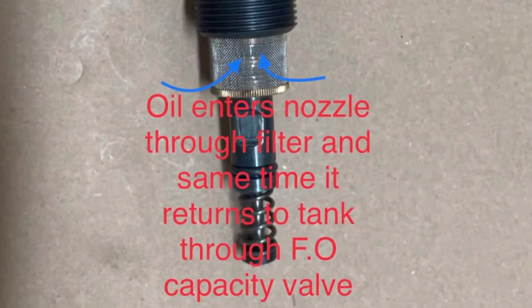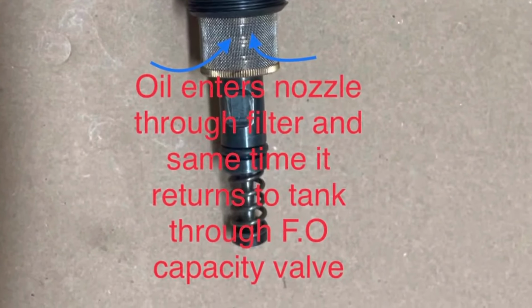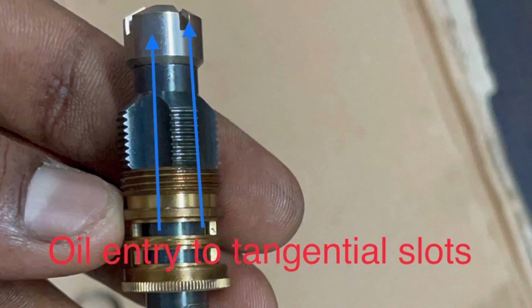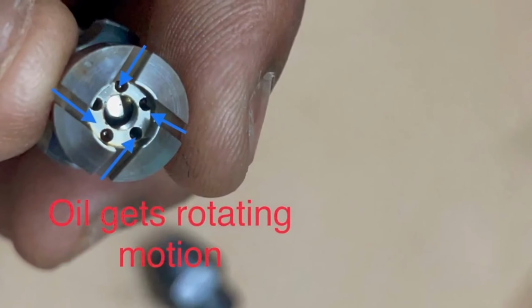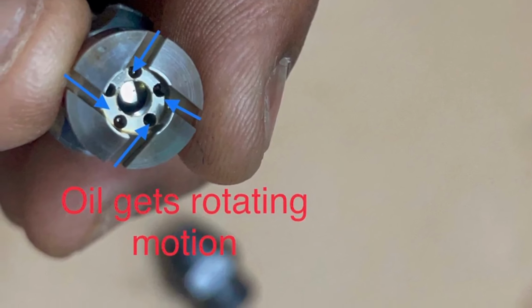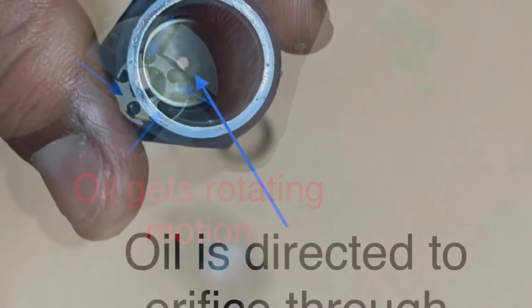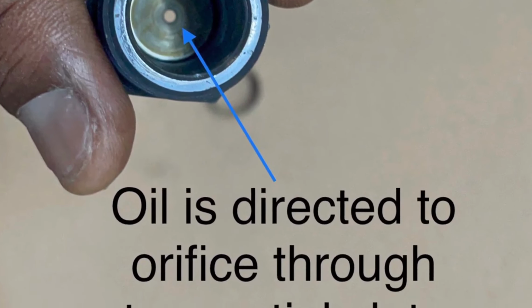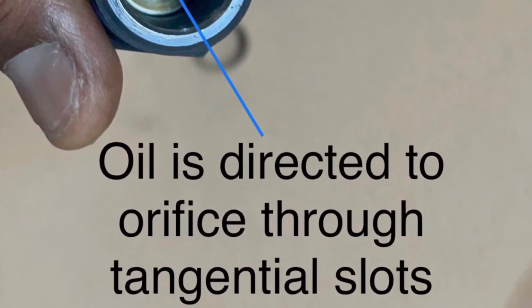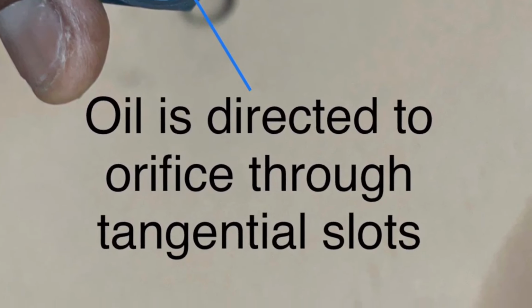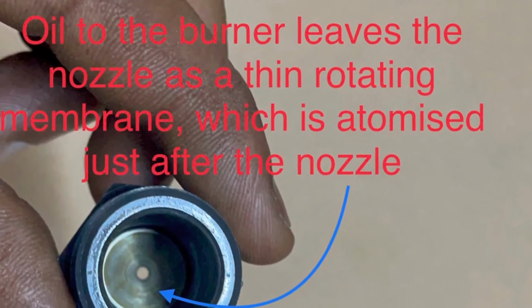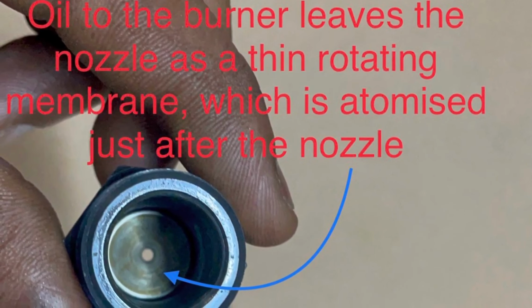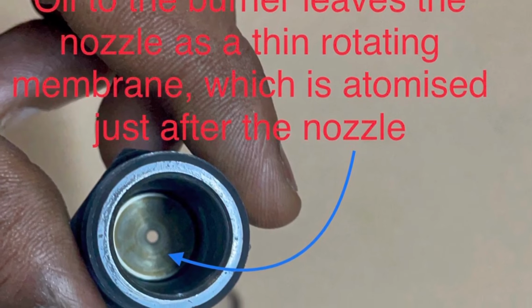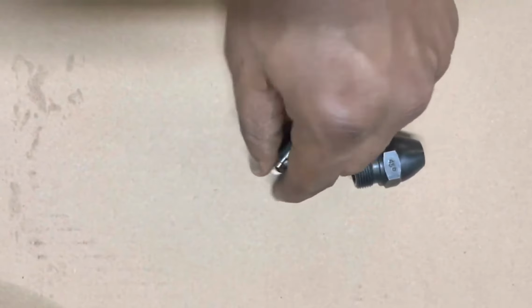The oil gets to the tangential slots through the filter. Because of the tangential slots, the oil gets a rotating motion and is directed to the orifice. The oil leaves the orifice as a thin rotating membrane, which is atomized just after the nozzle. The atomized oil forms a cone inside the generator, in which the top angle of the cone depends on the nozzle type and oil pressure.